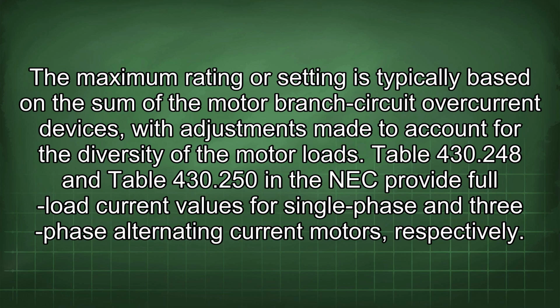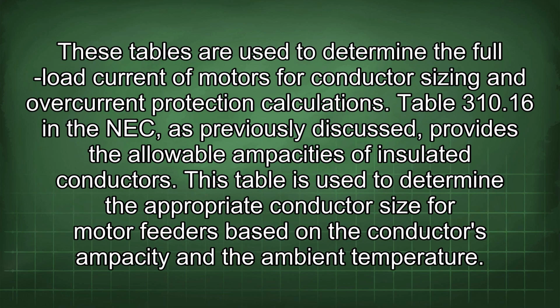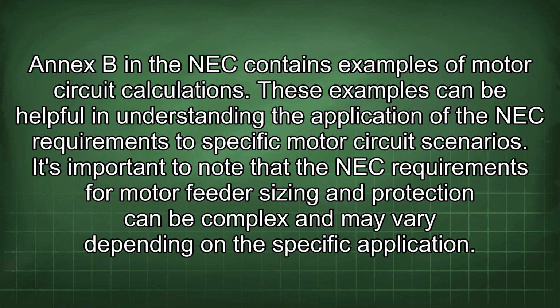Table 430.248 and Table 430.250 in the NEC provide full load current values for single-phase and three-phase alternating current motors, respectively. These tables are used to determine the full load current of motors for conductor sizing and overcurrent protection calculations. Table 310.16 in the NEC, as previously discussed, provides the allowable ampacities of insulated conductors. This table is used to determine the appropriate conductor size for motor feeders based on the conductor's ampacity and the ambient temperature. Annex B in the NEC contains examples of motor circuit calculations.